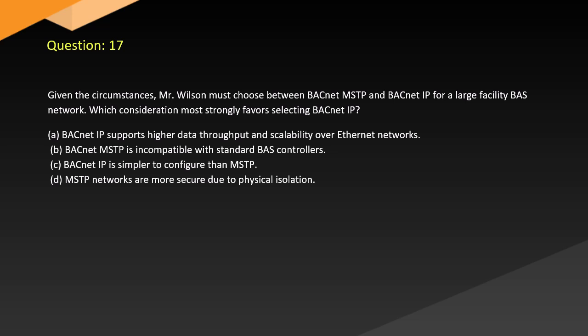Question 17. Given the circumstances, Mr. Wilson must choose between BACnet MS/TP and BACnet IP for a large facility BAS network. Which consideration most strongly favors selecting BACnet IP? A. BACnet IP supports higher data throughput and scalability over Ethernet networks. B. BACnet MS/TP is incompatible with standard BAS controllers. C. BACnet IP is simpler to configure than MS/TP. D. MS/TP networks are more secure due to physical isolation.